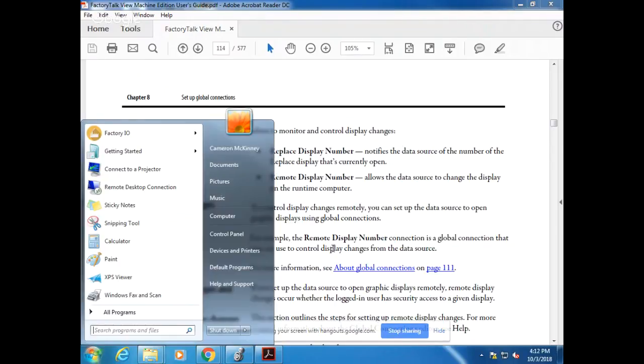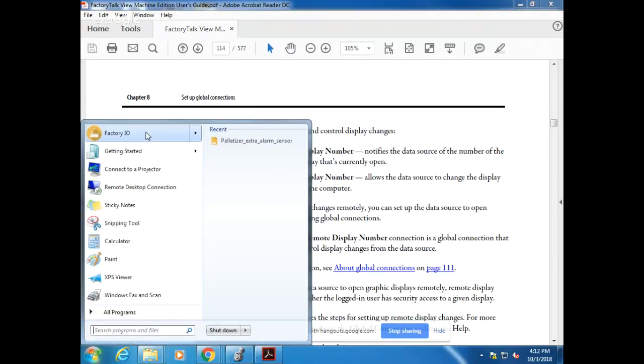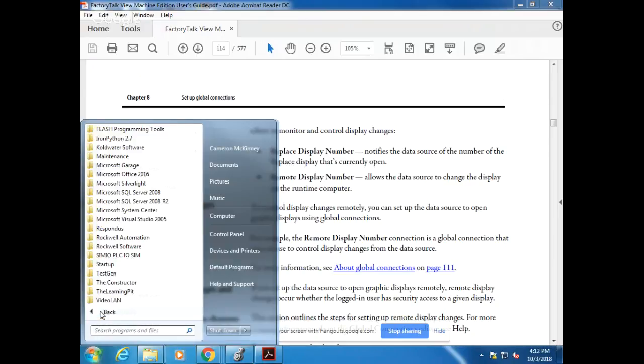Communications? No, you have to set all that back up. I'll be honest with you, every time you download to a PanelView, you should check the little box that says apply communication path update. I've just had issues not doing that in the past. They may have gotten better at it. I don't know.